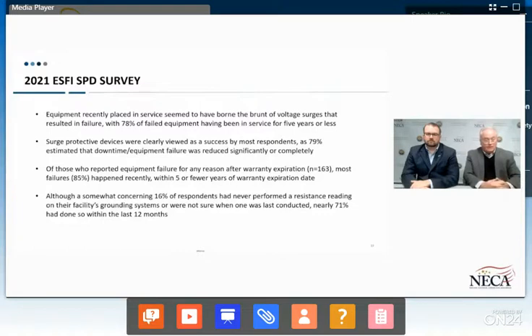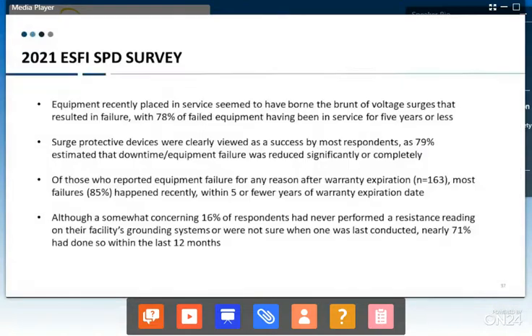Emergency system panel boards and switchboards, many of the new generations of equipment have electronics in them. If those systems were to fail, we're talking about life safety systems for a building, getting people out of buildings and things of that nature. So there's a lot of evolution going on that's resulting in requirements for surge protective devices.